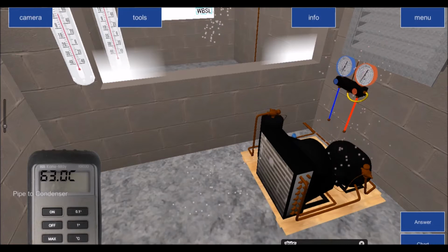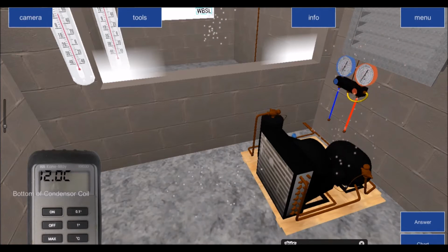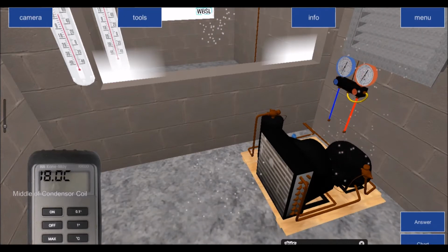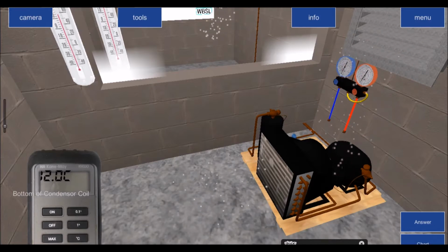You can see the temperature of the refrigerant is 63 degrees Celsius. We have the condensing zone, which is the middle of the condenser, and you can see our condensing temperature is 18 degrees Celsius. And we have the subcooling zone, so we can see that the temperature of the refrigerant at the bottom of the condenser is 12 degrees Celsius. And we know that the difference between the condensing zone and the subcooling zone, so the temperature at the middle of our condenser and the sensible temperature at the bottom of our condenser, is our subcooling value.